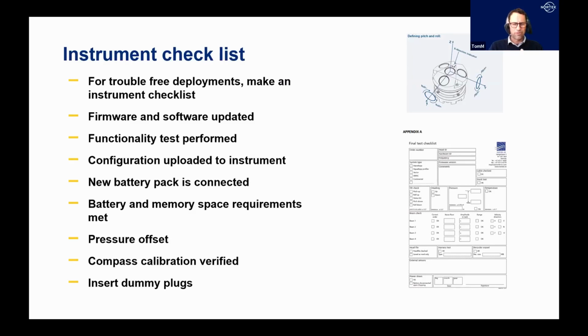Pressure offset: we do see people putting out the instrument with a pressure offset of 10 meters, for instance, still present. So calibrate the pressure before you go into the field.